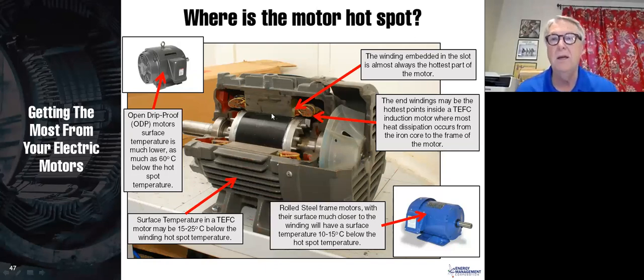Now, if you don't have a temperature measurement device, is the motor too hot or is it not? Well, here's an open drip proof motor. On the upper left here, the air goes through the motor. And because the air pretty much is between that outer frame and the inner rotor, it's very difficult to determine whether that motor is overheating by simply feeling or measuring the outside temperature of the motor. So unfortunately, we're kind of lost there.